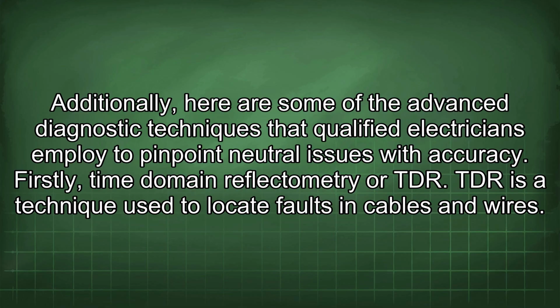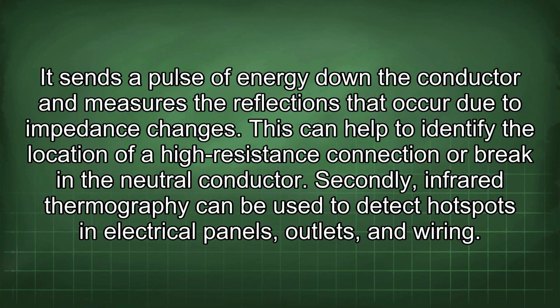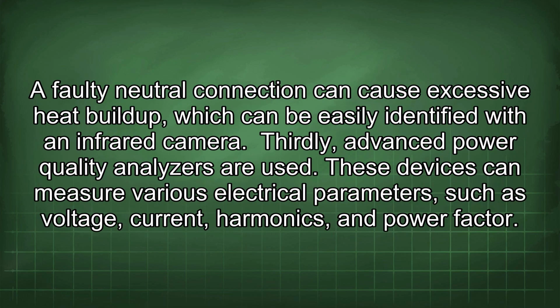TDR is a technique used to locate faults in cables and wires. It sends a pulse of energy down the conductor and measures the reflections that occur due to impedance changes. This can help to identify the location of a high resistance connection or break in the neutral conductor. Secondly, infrared thermography can be used to detect hotspots in electrical panels, outlets, and wiring. A faulty neutral connection can cause excessive heat buildup, which can be easily identified with an infrared camera.